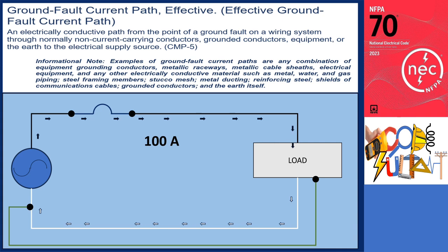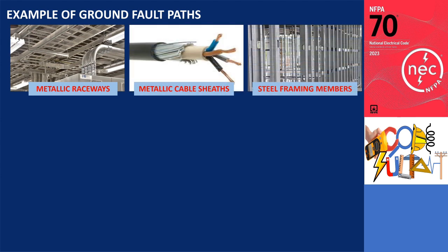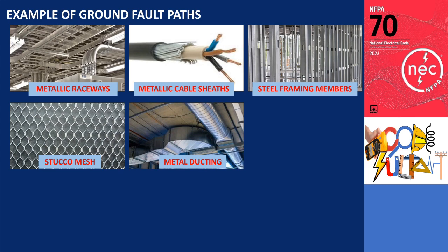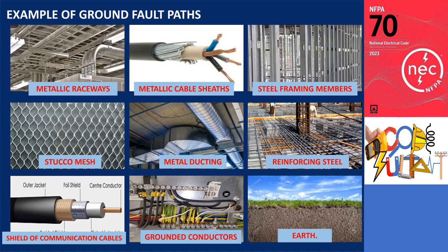The effective ground fault current path is defined as an electrically conductive path from the point of a ground fault on a wiring system through normally non-current carrying conductors, grounded conductors, equipment, or the Earth to the electrical supply source. Going back to the previous circuit with 100 amps, the green line is a ground fault current path, if this is made of conductors, metallic raceways, metallic cable sheaths, electrical equipment, and any other electrically conductive material such as metal, water, and gas piping, steel framing members, stucco mesh, metal ducting, reinforcing steel, shields of communications cables, grounded conductors, and the Earth itself. This equipment grounding conductor is an effective ground fault path.